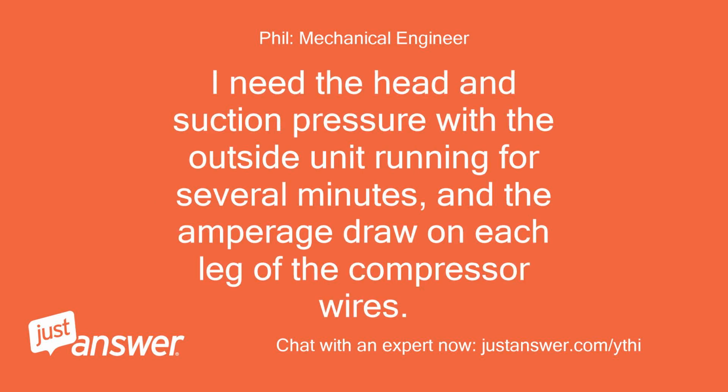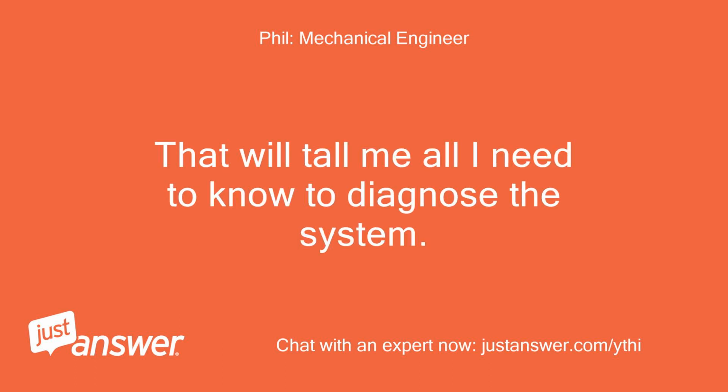I need the head and suction pressure with the outside unit running for several minutes, and the amperage draw on each leg of the compressor wires. That will tell me all I need to know to diagnose the system.